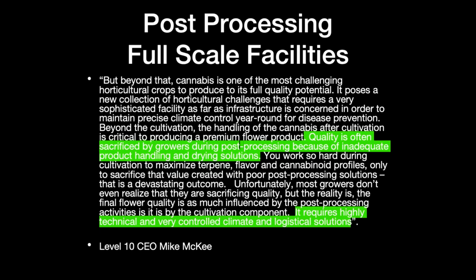But they don't want to pull off too much of it. So what you really got to do is stage the temperature and humidity control down over those first 4 to 5 days. And the target, generally speaking, that we're seeing is the growers will tell us, well, I want it at 60 and like 40% relative humidity. If you look at 60 and 40% relative humidity in a space, it's very hard to take any moisture out of that space because you're limited by your suction temperature. The only way to essentially do something like that would be with active desiccant dehumidification.